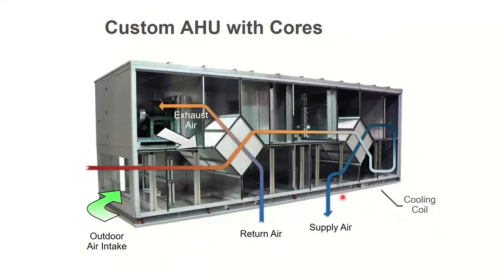You can also use it for certain applications where you might want some free reheat. So in this case, we have two cores. It could be wheels, but this one's cores. The return air is coming in, releasing its energy and going out the exhaust. The fresh air comes in, gets the free energy, then comes around and goes through another core where it releases more energy, goes through a cooling coil to get cooled way down below the dew point and pull a lot of moisture out of there. And then it wraps around and it picks up the heat it just left off.